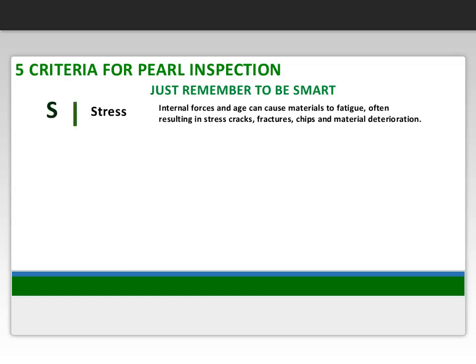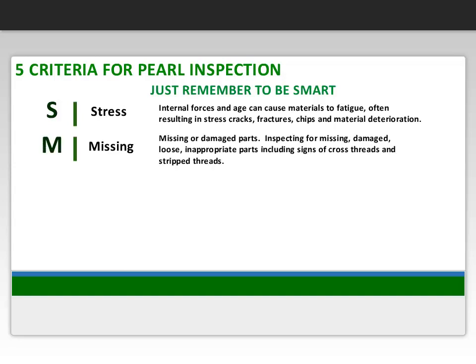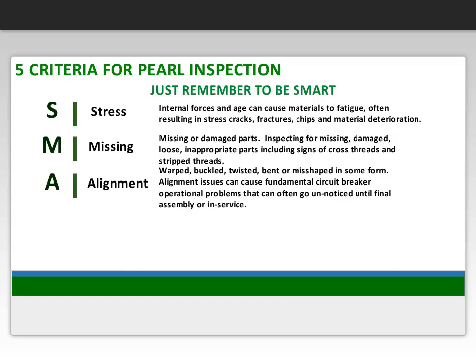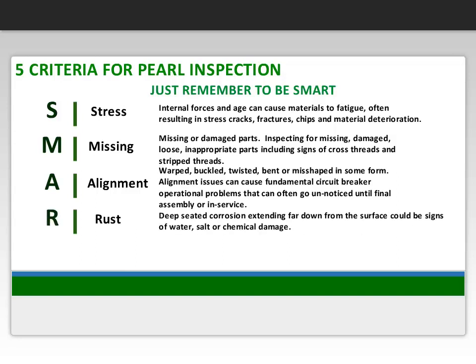S is for stress. Internal forces and age can cause materials to fatigue, often resulting in stress cracks, fractures, chips, and material deterioration. M is for missing items or parts. Inspect for missing, damaged, loose, inappropriate parts, including signs of cross threads and stripped threads. Alignment is the A. Warped, buckled, twisted, bent, or misshaped in some form. Alignment issues can cause fundamental circuit breaker operational problems that can often go unnoticed until final assembly or in service. R is to look for rust. Deep-seated corrosion extending far down from the surface could be signs of water, salt, or chemical damage.